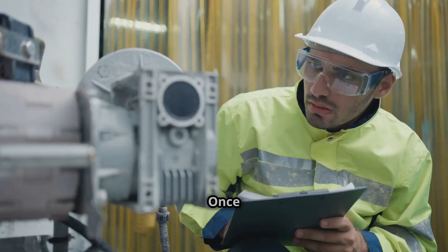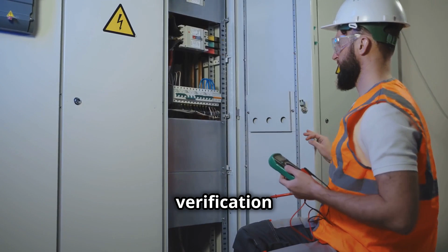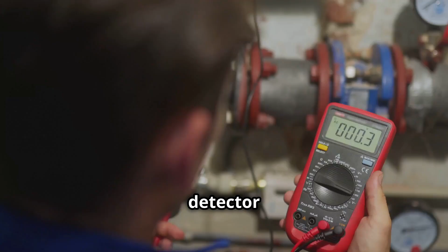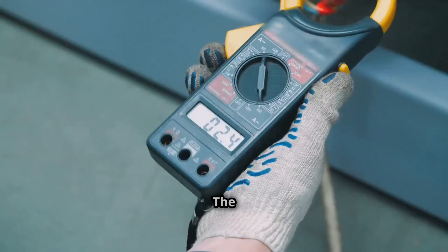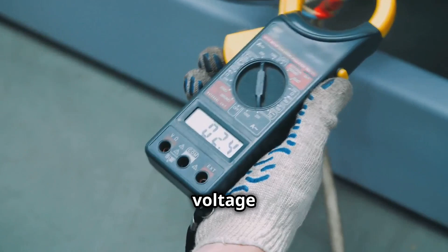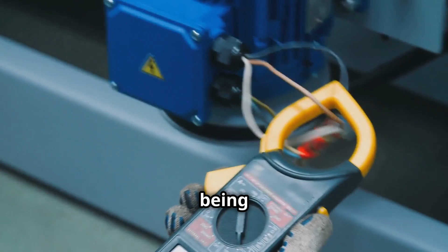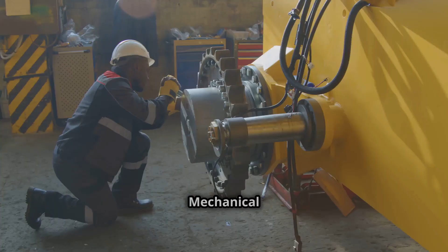Once the energy isolating devices have been locked out and tagged out, it's essential to verify that the isolation is complete and effective. This involves physically checking that the energy sources have been disconnected and that no residual energy remains in the system. For electrical systems, verification typically involves using a voltage detector or multimeter to test for the presence of voltage at the point of work. The voltage detector should be rated for the specific voltage level of the system being tested. Never rely solely on visual inspection of switches or circuit breakers, as they may be faulty or incorrectly labeled.